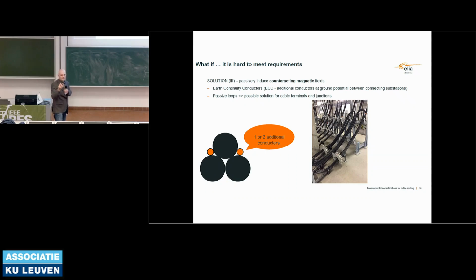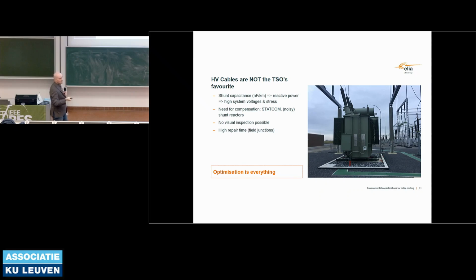But all the solutions I've shown already suppose that the cables are really close together and don't fan out, like for example in junction pits or at cable terminals in a substation. So for those installations, we have what we call, still kind of in experimental mode, these passive meshes or passive circles, I don't know how to call them in English. So even with a toroidal core around them, just to force this counter-magnetic flux, in order to reduce to a maximum the radiated or emitted magnetic fields.